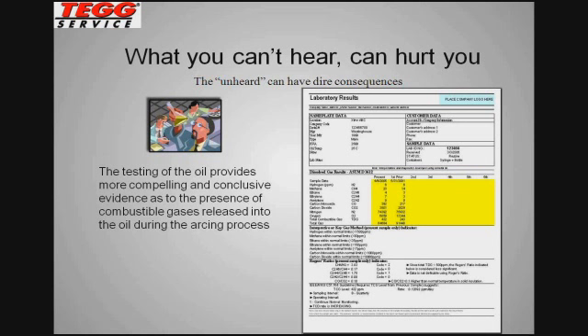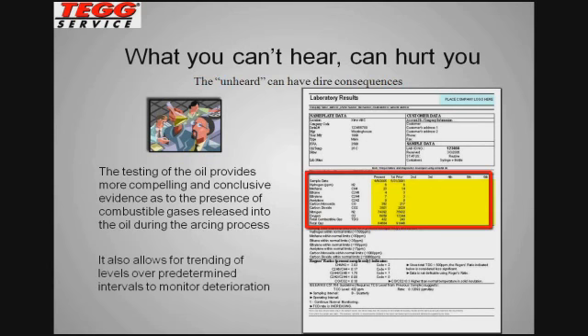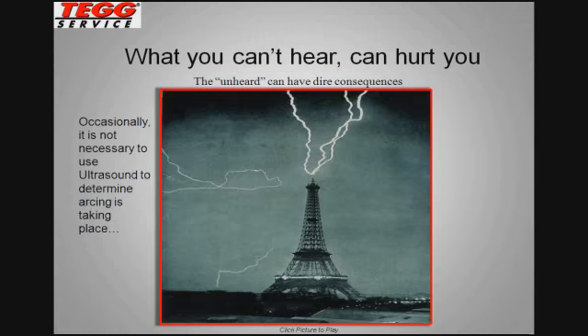And the customer began to trend the dissolved gas in oil analysis results over the next 6 to 12 months. And with an increase in those values, things like acetylene and methane, the combustible gases, that would indicate that the unit is in fact deteriorating and back up what we had found with the ultraprobe, which was the early stages of the arcing that was taking place inside.